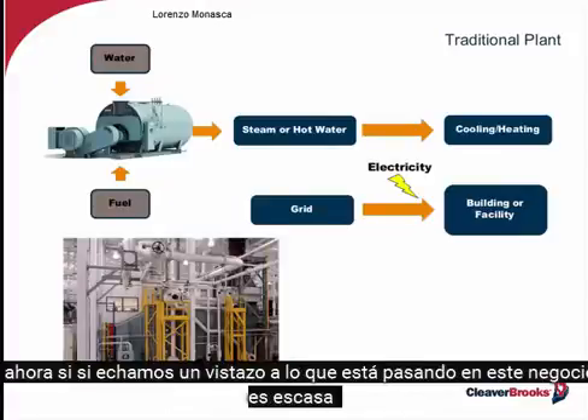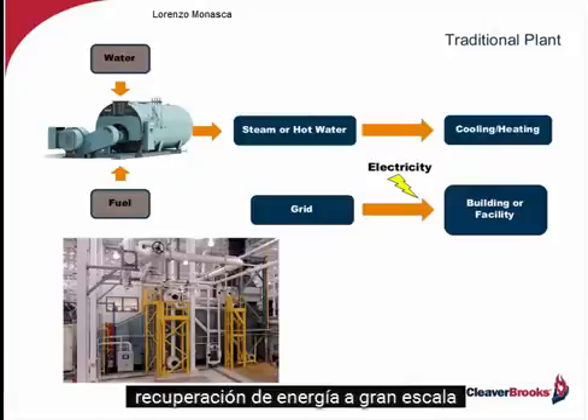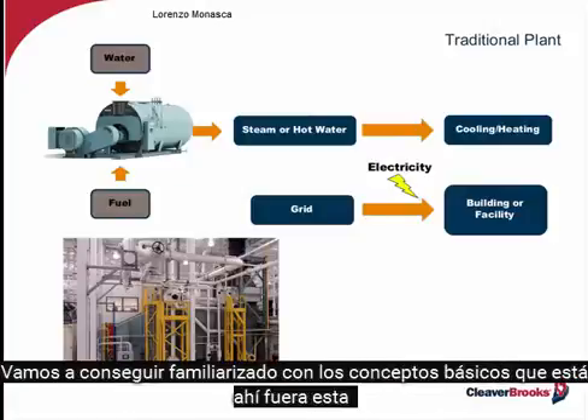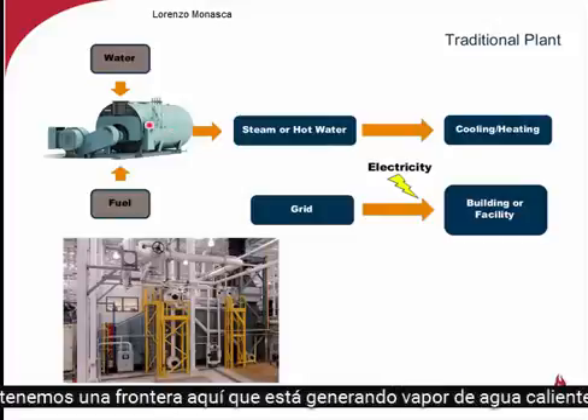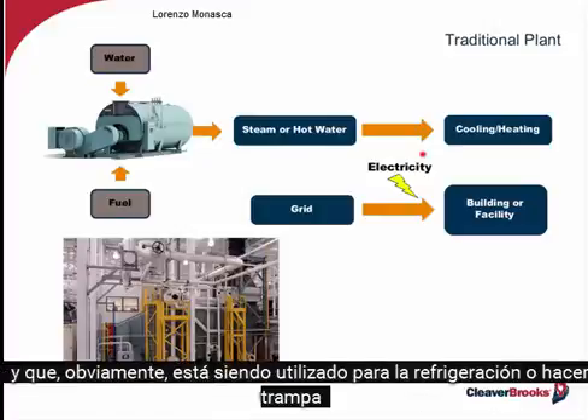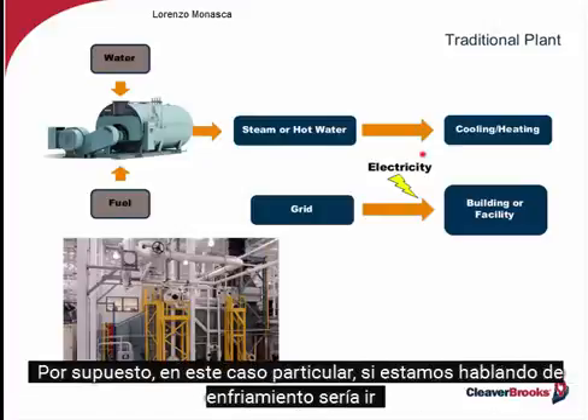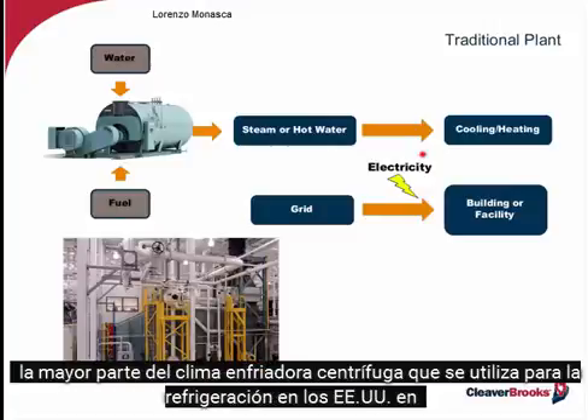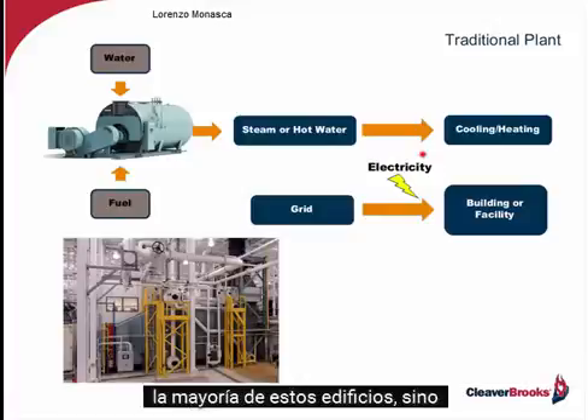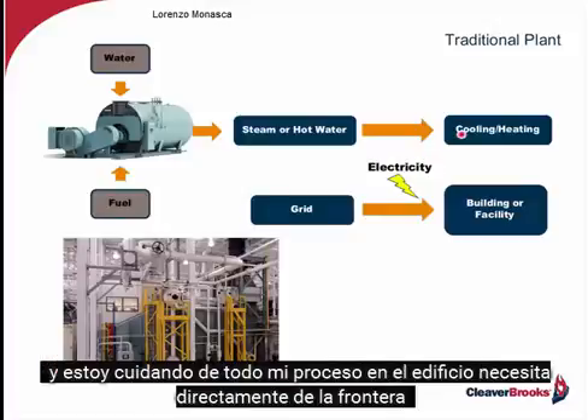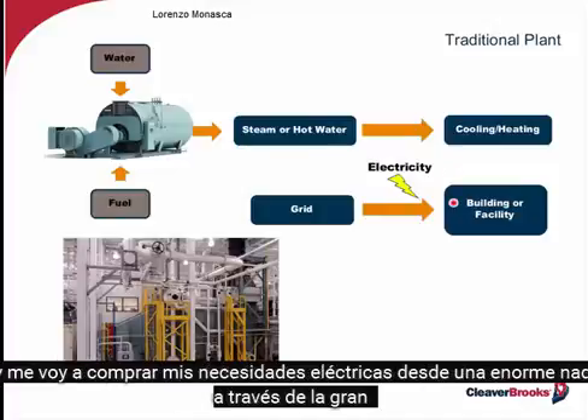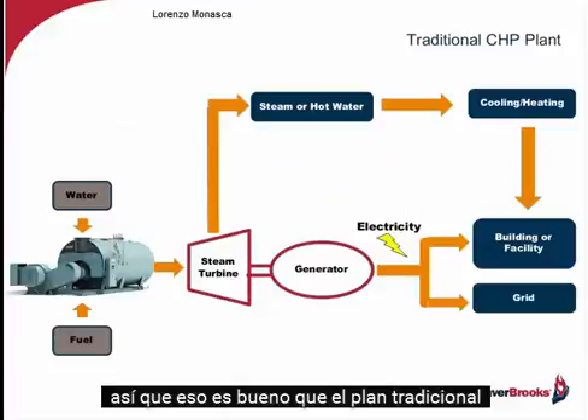Now, if we take a look at what's going on in this business as far as large-scale energy recovery, let's just familiarize ourselves with the basic concepts that are out there. This is the traditional plant. We've got a boiler here that's generating steam or hot water, and that's obviously being used for cooling or heating. Of course, in this particular case, if we're talking about cooling, it would be going to an absorber. Most of the time, it's a centrifugal chiller that's used for cooling in most of these buildings, but just for example's sake. So I'm taking the steam, and I'm taking care of all my process and building needs directly from the boiler. Then I'm buying my electrical needs right from a utility through the grid. So that's the traditional plant.